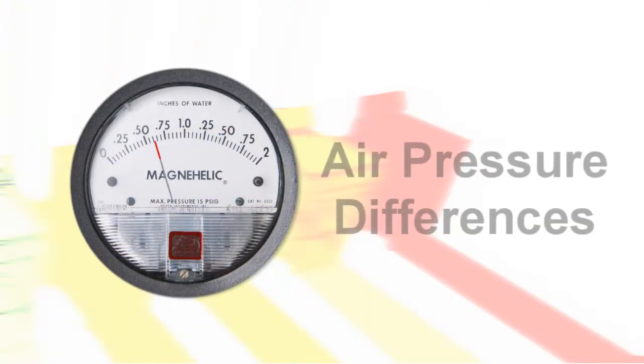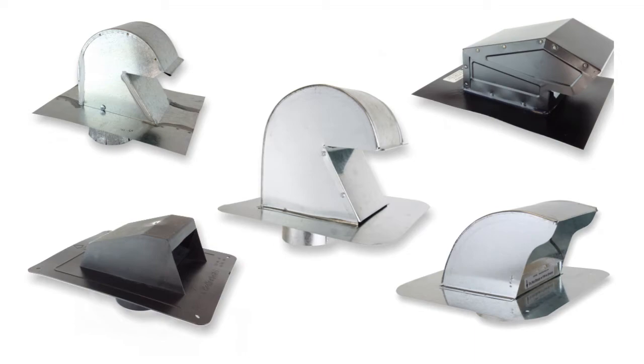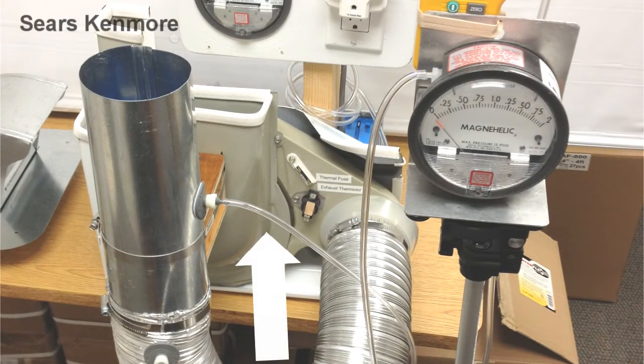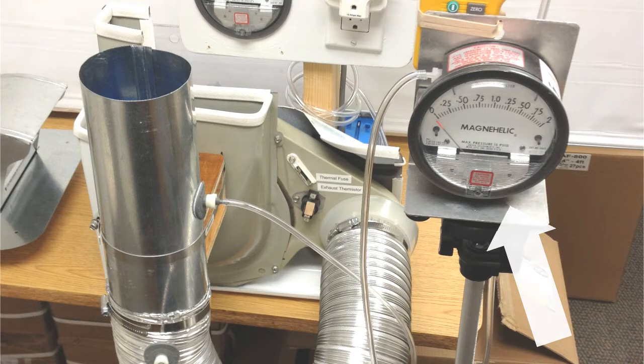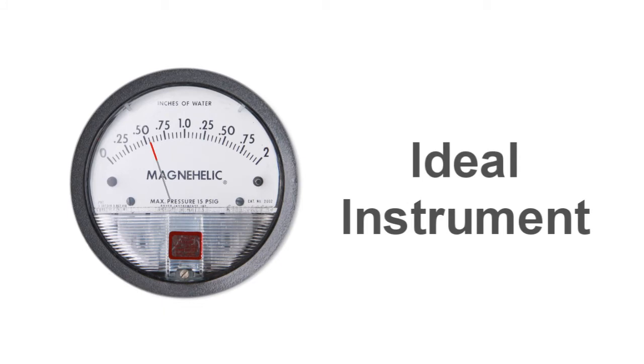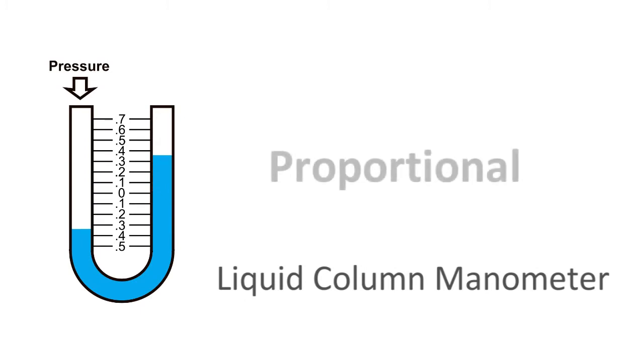This video will reveal the actual air pressure differences produced in five popular vent hoods. Our test apparatus comprises the actual blower unit from a Kenmore dryer and a Magnehelic gauge. In our industry, the Magnehelic gauge is the ideal instrument to accurately display the subtle levels in dryer exhaust, and works similarly to a liquid column manometer where the difference in fluid height is proportional to the pressure difference.